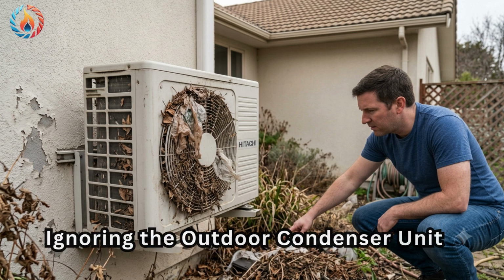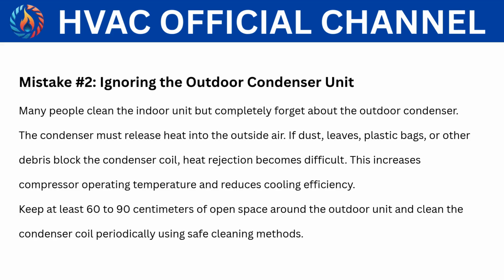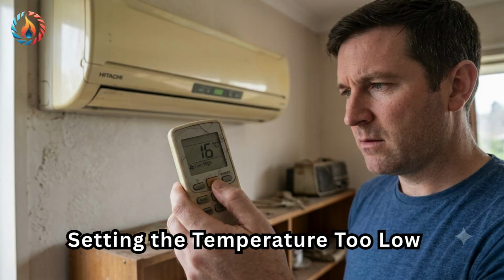Mistake number 2. Ignoring the outdoor condenser unit. Many people clean the indoor unit but completely forget about the outdoor condenser. The condenser must release heat into the outside air. If dust, leaves, plastic bags, or other debris block the condenser coil, heat rejection becomes difficult. This increases compressor operating temperature and reduces cooling efficiency. Keep at least 60 to 90 centimeters of open space around the outdoor unit and clean the condenser coil periodically using safe cleaning methods.